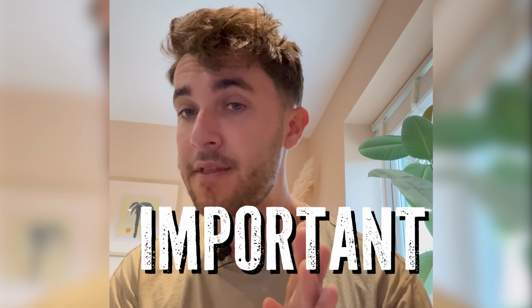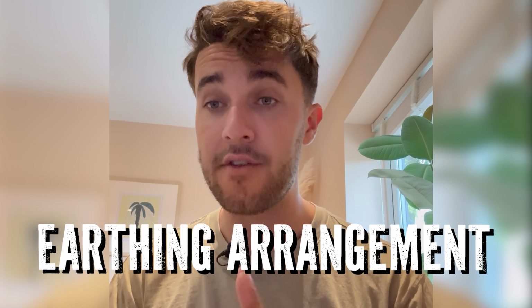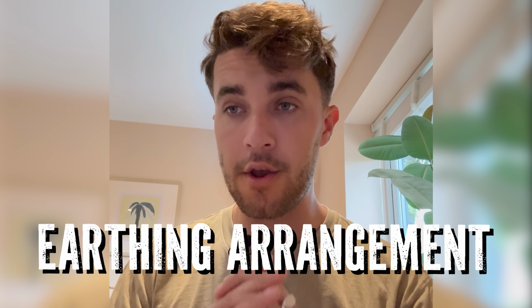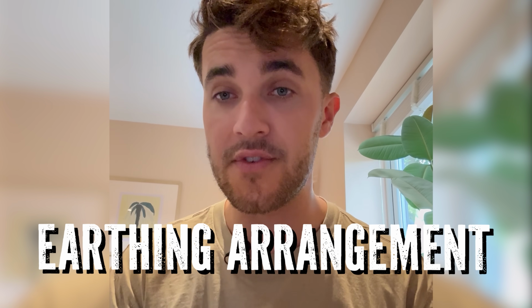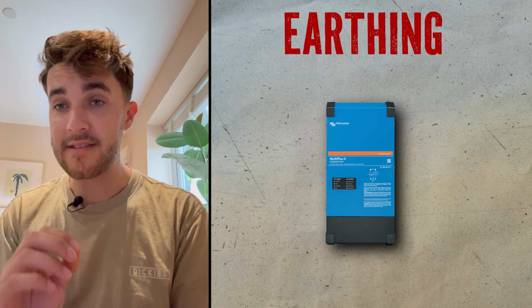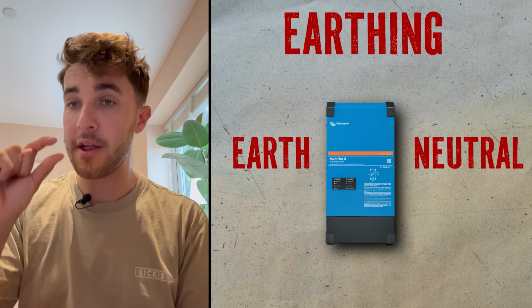The most important thing, I'd argue, is your earthing arrangement. You need to install an earth rod for your off-grid electrical system, and make sure to select an inverter that will bond your earth and your neutral together.